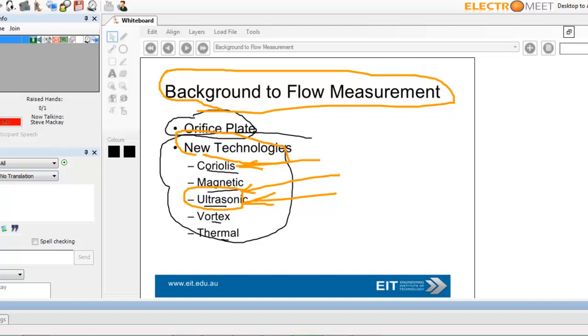Advantages, very high accuracy, no pressure drop because you've got no obstruction, non-intrusive, and approved for custody transfer of gas and liquids. Biggest problems are cost, clean fluids, and it's a little bit of problems with swirl. So the kind of guys that promote this are Siemens, GE Measurement, Emerson Daniel, and Elster.